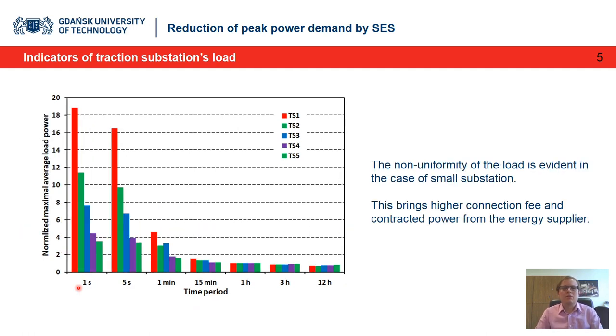To present this better, here is the same comparison for the same substations, rescaled to the 1 hour average traction value of the traction substation. We see, especially in the smallest substations TS1 and TS2, which supply only one supply section, that the momentary value at 1 second or 5 second scale is around 20 times bigger than the load power value at the 1 hour scale.